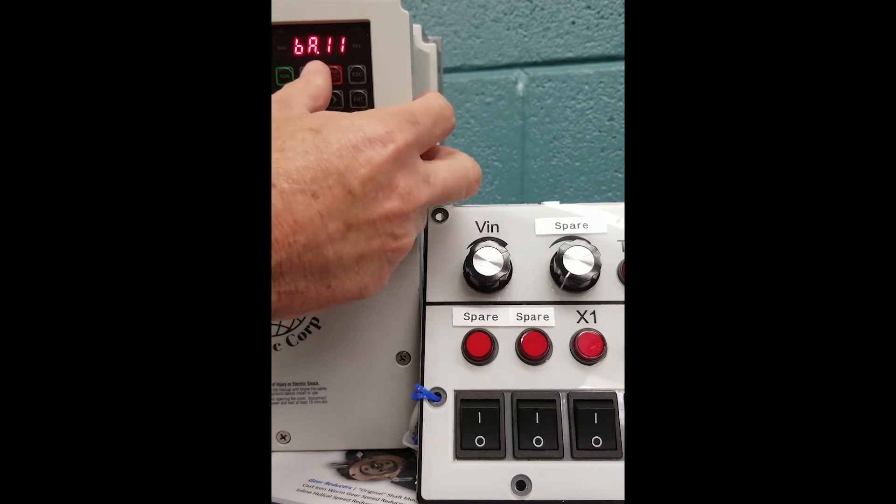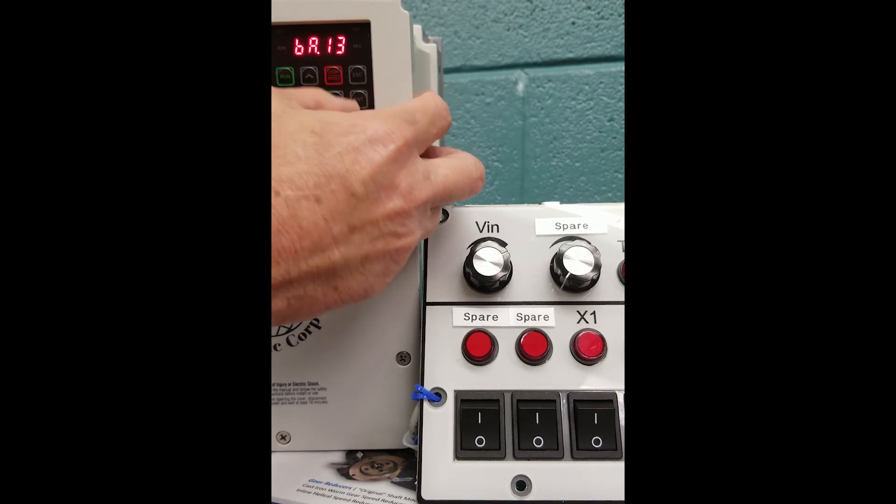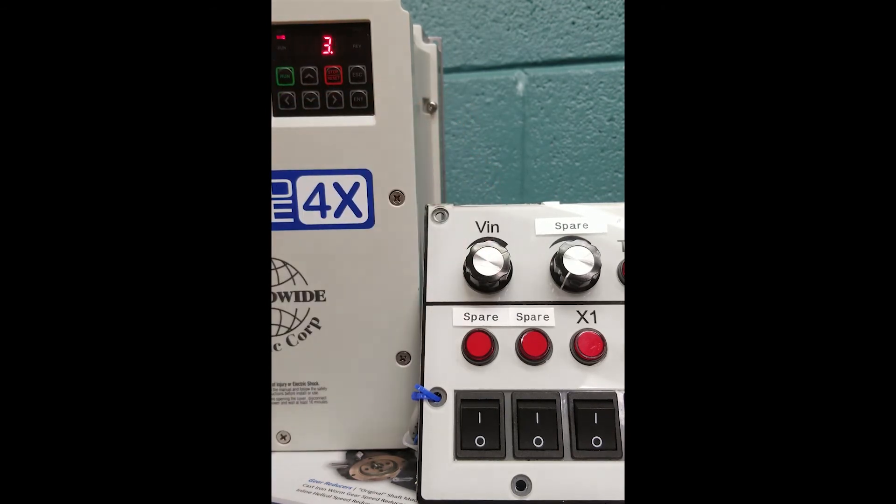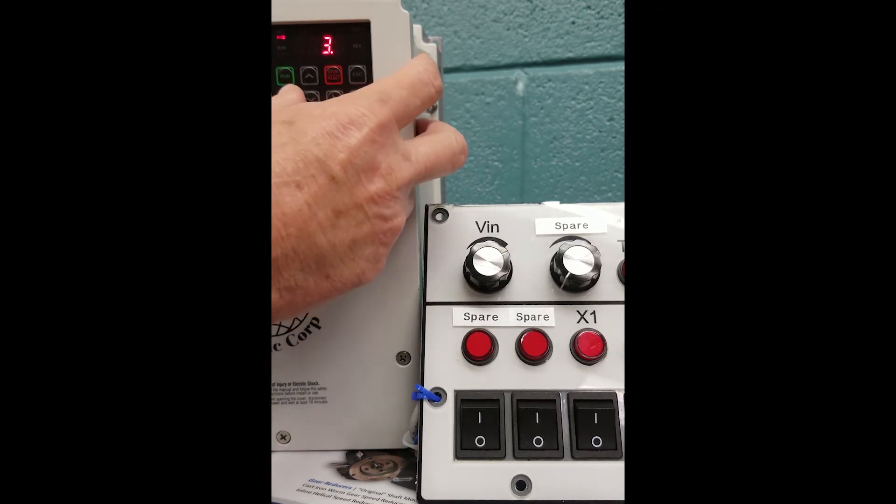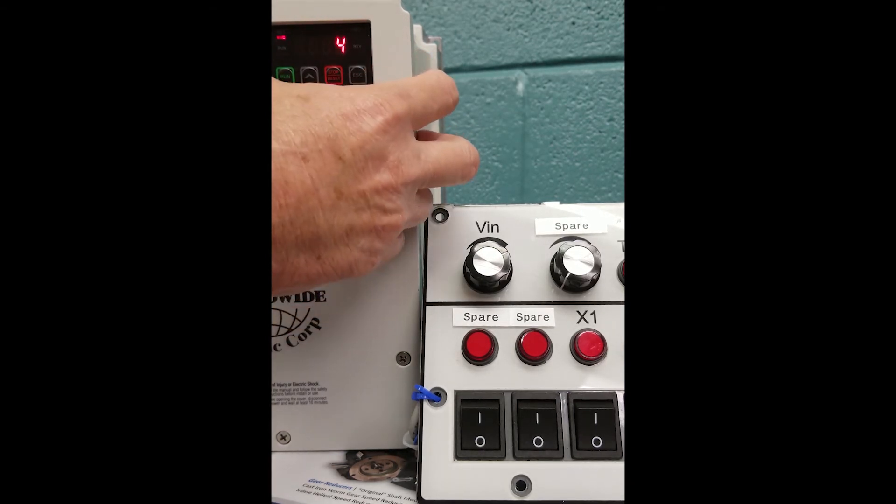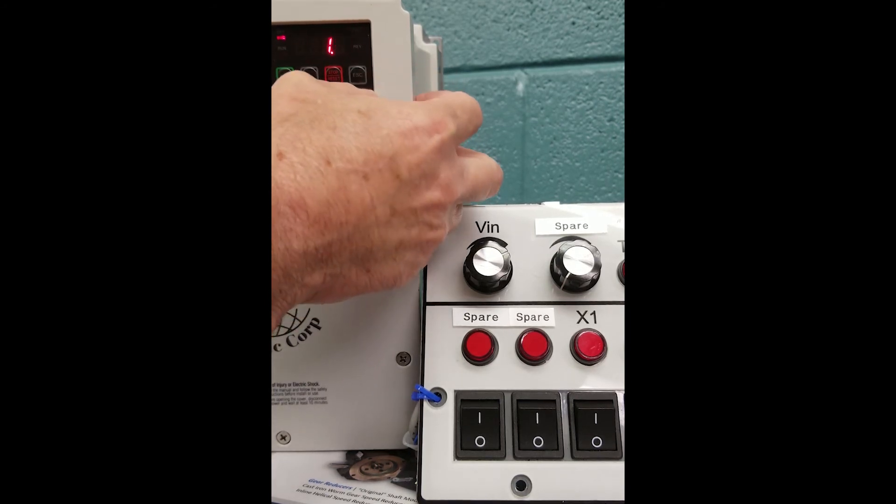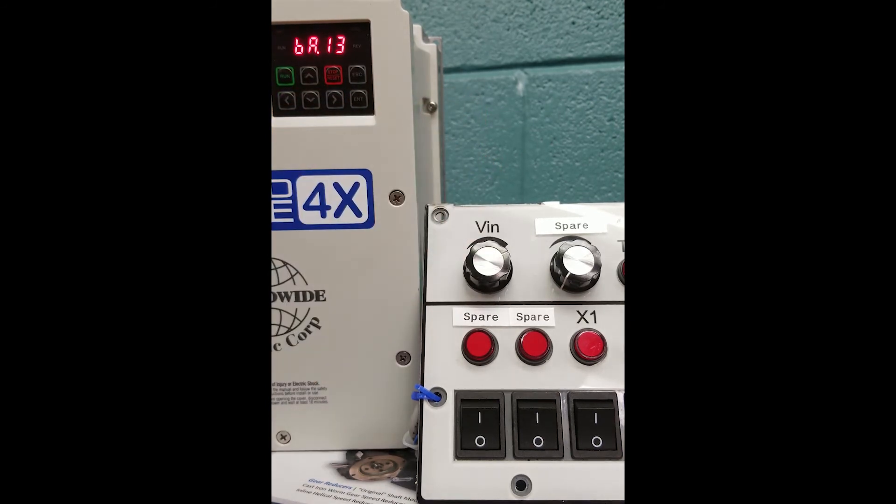We are going to go to BA 13. Hit enter. BA 13 is the full load amps of our motor, factory default at 3.4. Our motor today is 1.7, so we're going to change the 3.4 using our arrow keys over to 1.7. Again, hitting enter twice to store it.